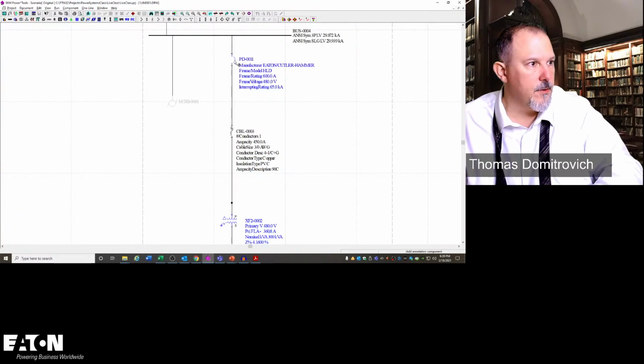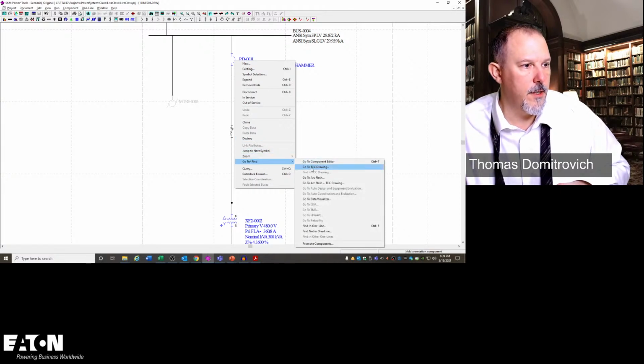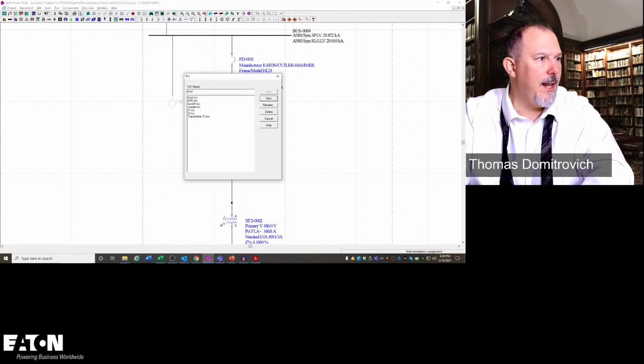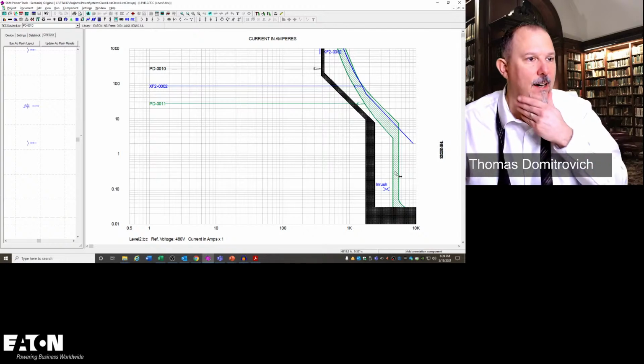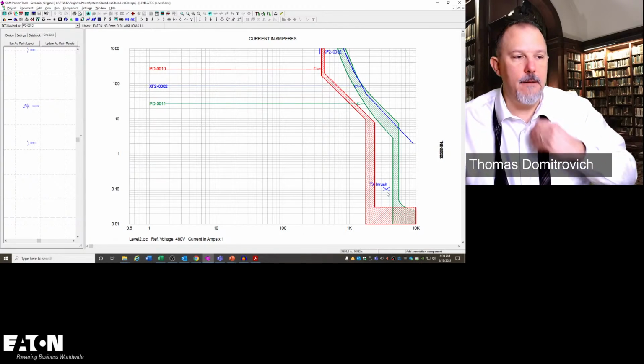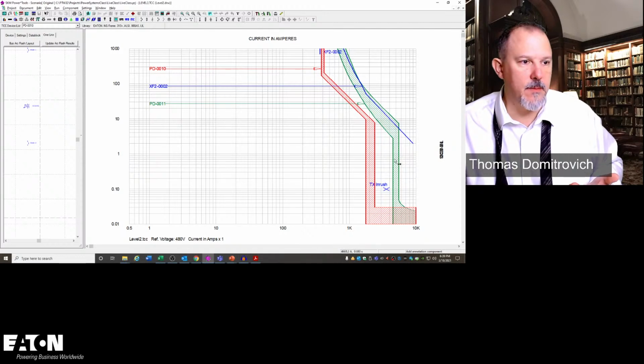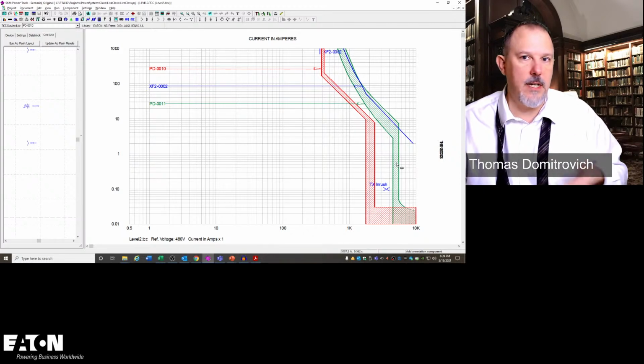I am going to select all three of these breakers, and go to the TCC drawing. I'm going to call this level 2. Okay, now this is my primary breaker, and this is my secondary breaker. The primary breaker is not going to see all 14,000 amps or 12,844 amps. It's only going to see 5,566 amps.